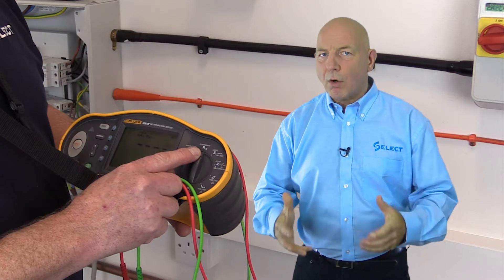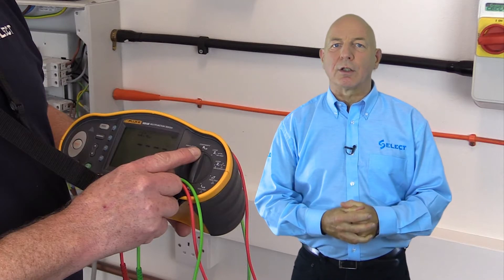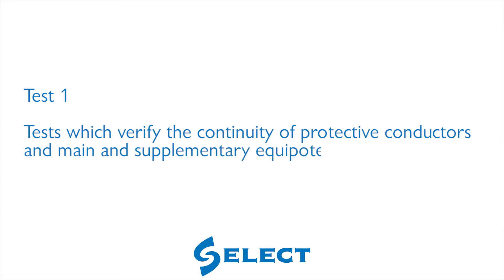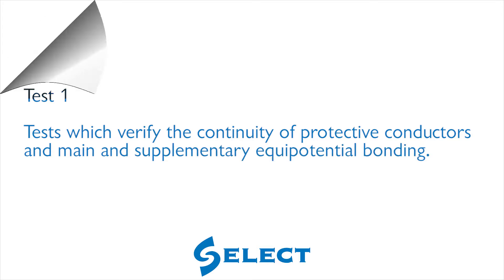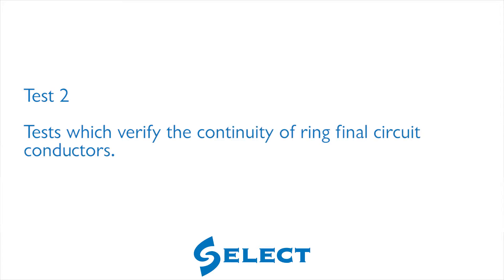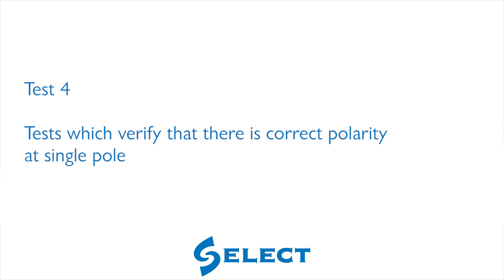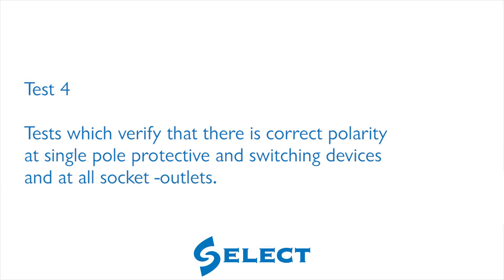The power-off tests demonstrated include Test 1, which verifies the continuity of protective conductors and main and supplementary equipotential bonding. Test 2, which verifies the continuity of ring final circuit conductors. Test 3 tests that the insulation resistance is satisfactory. And Test 4, which verifies that there is correct polarity at the single pole protective and switching devices and at all socket outlets.